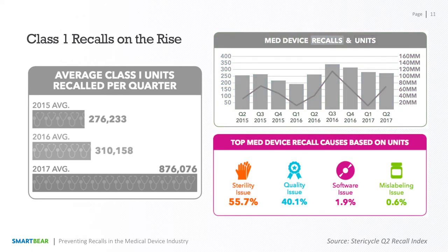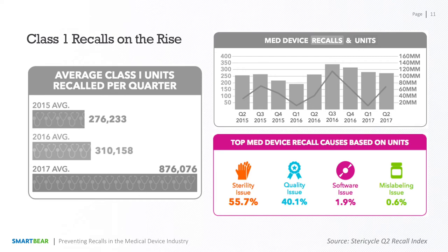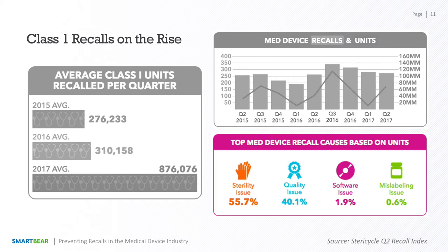So what caused these recalls? The majority of units were recalled due to sterility issues, and these are typically the kinds of units that don't have software as a component. For the rest of this webinar, we're mostly going to focus on the recalls that were triggered by quality issues and software issues. While software was the primary issue for only 1.9% of the recalls, that translates to roughly 1.3 million units, and that number is likely to rise because there is now an example of software vulnerabilities in medical devices being seen as a financial opportunity.